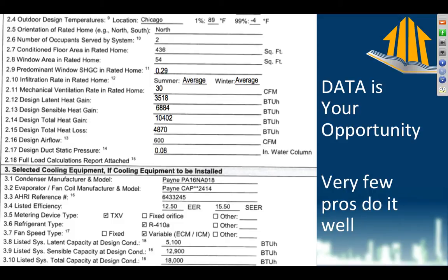Now the next thing is where we get into the weeds here. These three numbers. The first number, which is 2.12, this is the design latent heat gain. The second thing that you see there, 2.13, is the design sensible heat gain. Now let's forget about the total for a minute and just talk about these two. Sensible heat is temperature. That's the temperature that you can feel. Latent heat is the heat that exists in air when there is humidity in it. And that has to do with if that humidity were to fall out of the air, we have this possibility of raising the air temperature because of that, or lowering it if we were to do condensing, evaporation, do different things. So basically, evaporation is going to lower the temperature of what's around it. Condensation is going to raise the temperature of what's around it. So both of these things are very important.